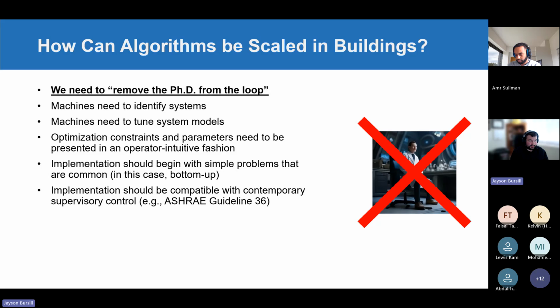So I've chosen to look at the zone first because it's a fairly simple problem, and it's a problem that can be duplicated a lot and take advantage of some of the technology that we're starting to see emerge as a prerequisite. Also, compatibility with other supervisory control systems - this is very control specific, and I'm referencing ASHRAE Guideline 36 here, but really anything that gives you an almost standard type language sequence you can reference, or anything that's contained in a spec. All of these systems need to be compatible with that, which lends to the modularity I've talked about above.